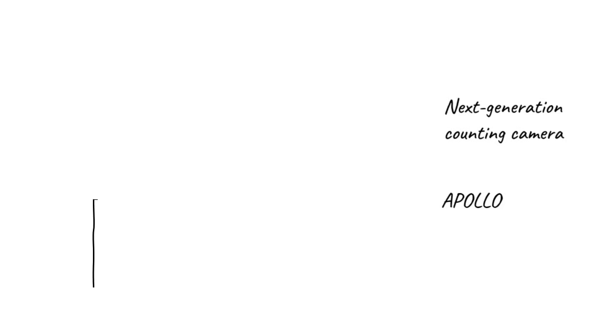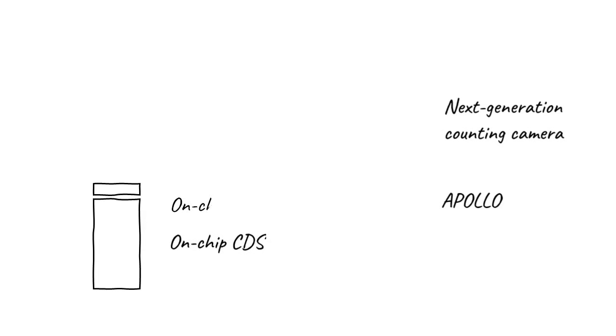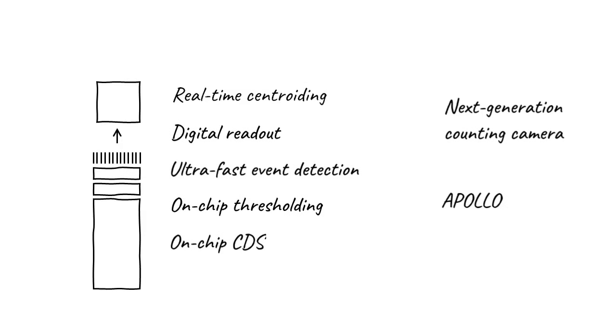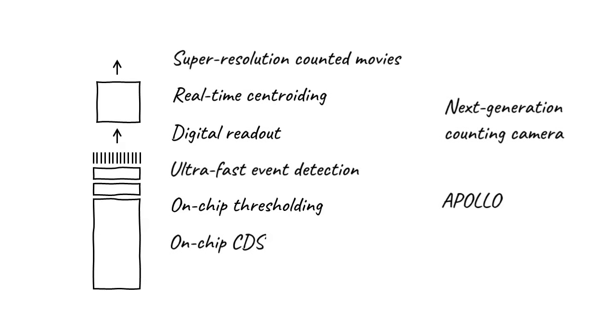Let's review what we've learned. Apollo's direct detection pixel array is designed with continuous on-chip CDS to minimize reset noise. Structures at the edge of the sensor perform on-chip thresholding to efficiently distinguish signal from noise. Signals are then packaged into event blocks for ultra-fast digital readout. Finally, FPGAs perform real-time centroiding of detection events, outputting a stream of super-resolution dose-fractionated movie frames, which are saved to an SSD array in open format such as MRC or TIFF-LZW.